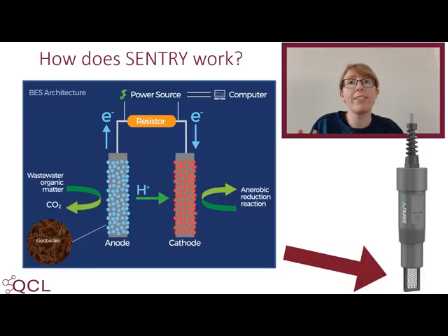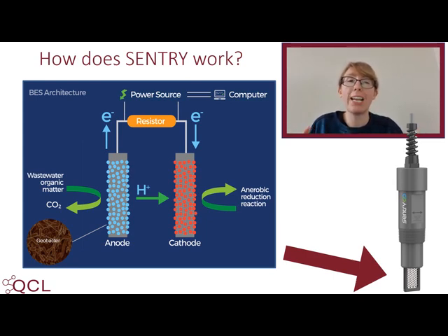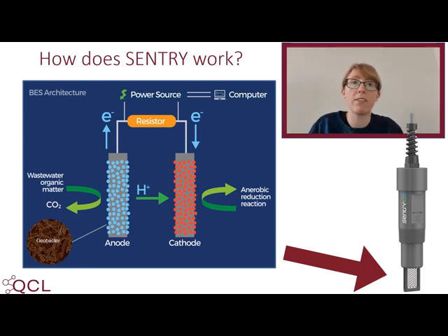Most sensors measure physiochemical properties — for instance pH, ORP, etc. — to act as a chemical proxy for understanding biology. However, Sentry directly measures the microbial metabolic activity of the microorganisms involved in wastewater treatment: the microbial electron transfer rate.